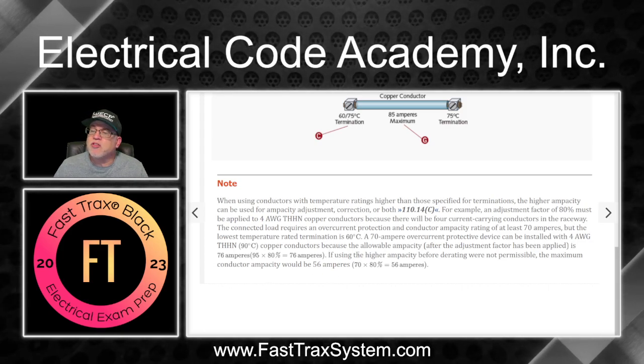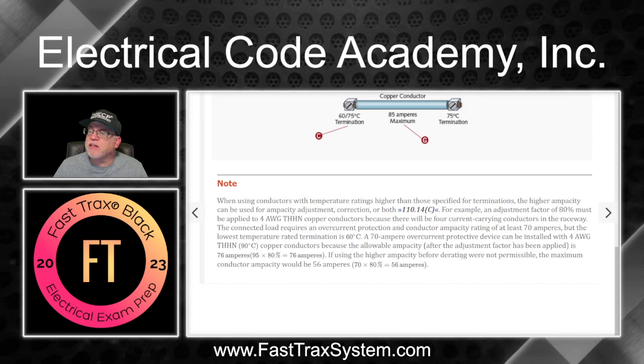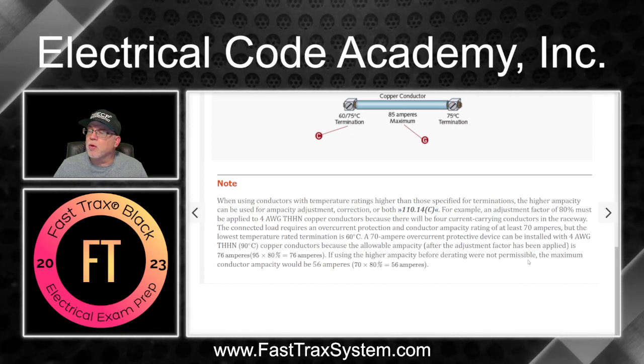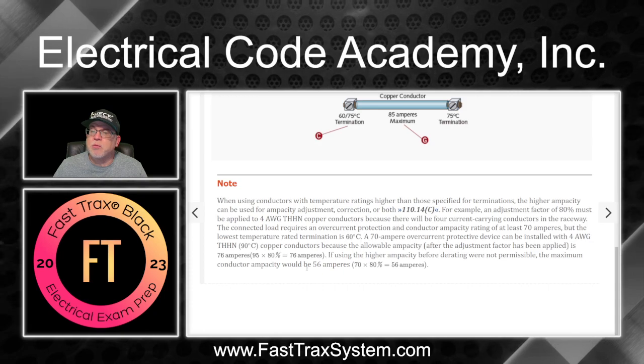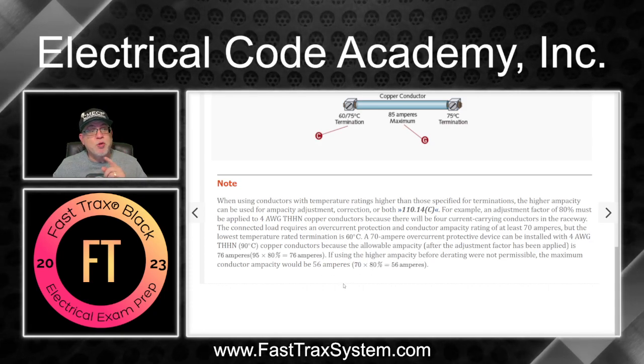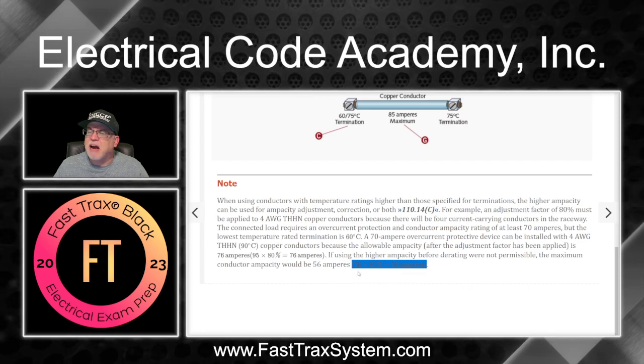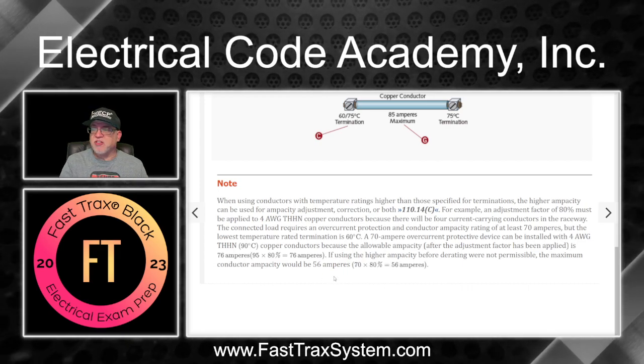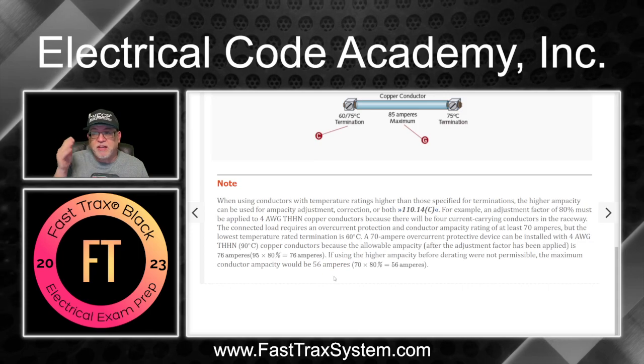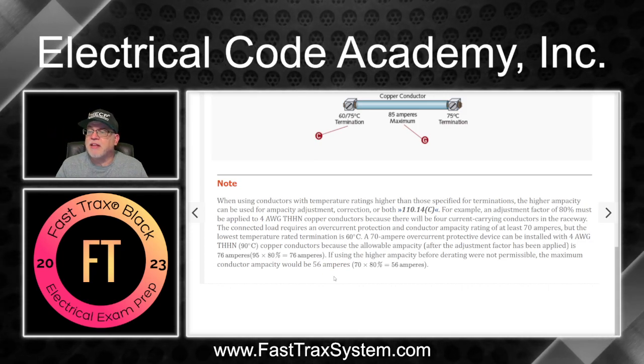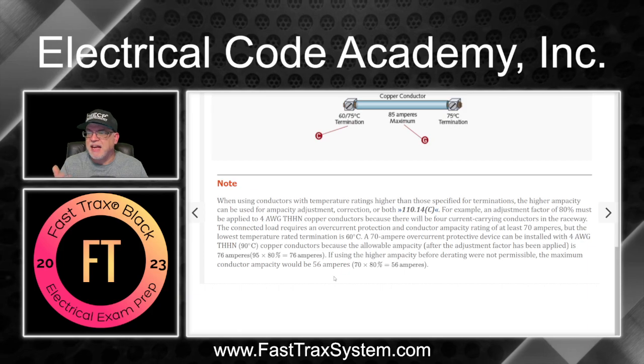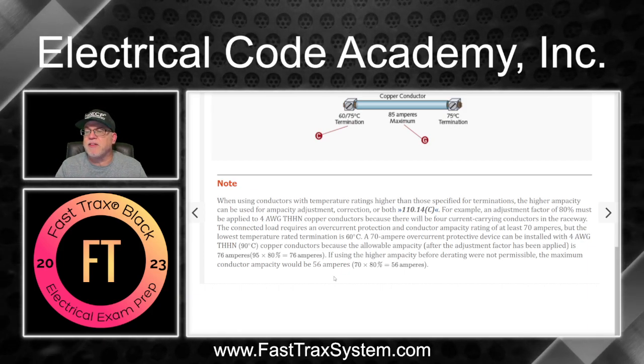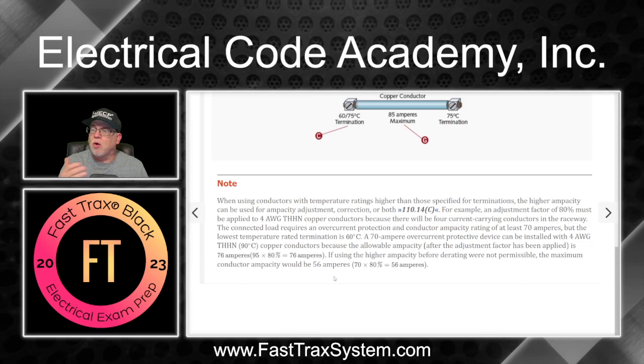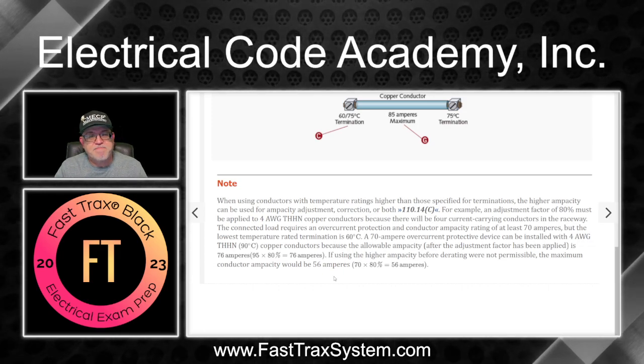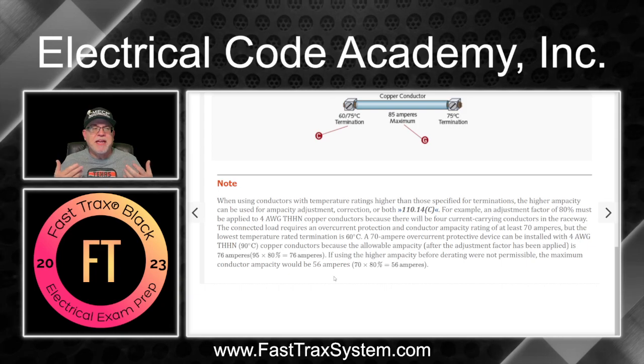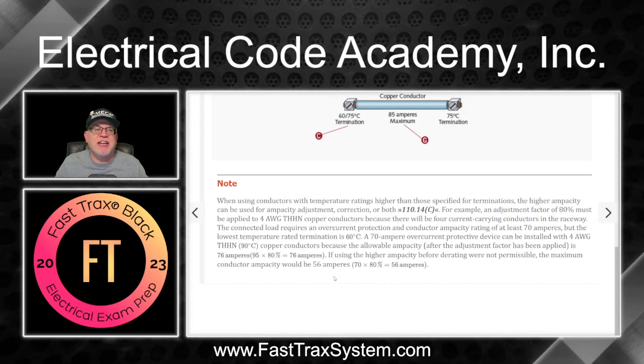So if using the higher ampacity before derating were not permissible, the maximum conductor ampacity would have been 56 amps. See, if you couldn't use that 90, then I would have had to do it from the 70, which is the 60-degree column, right? If I wasn't, because of the terminals, then I would have been screwed. Because at that point, 70 times 80% would have been 56 amps, and that's not going to work on a 70 amp overcurrent protected device, right? So that means you're not going to get as much out of the conductor as you expected.